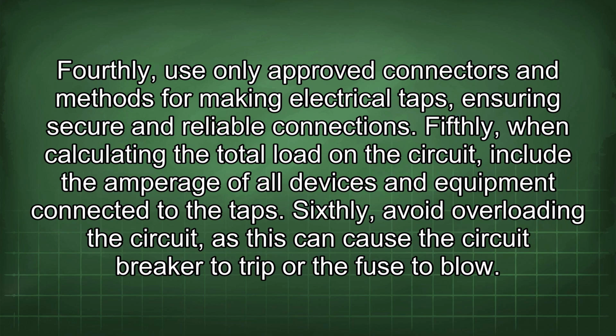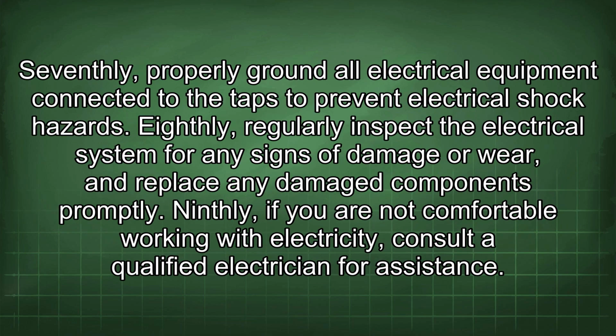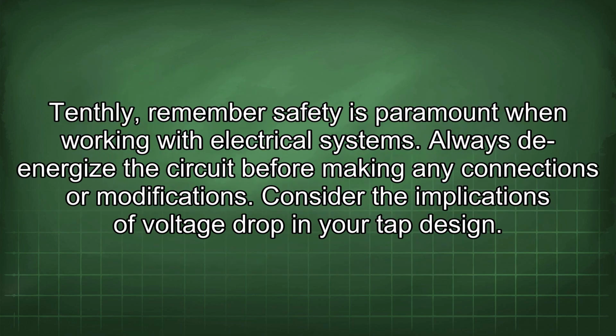Fifthly, when calculating the total load on the circuit, include the amperage of all devices and equipment connected to the taps. Sixthly, avoid overloading the circuit, as this can cause the circuit breaker to trip or the fuse to blow. Seventhly, properly ground all electrical equipment connected to the taps to prevent electrical shock hazards. Eighthly, regularly inspect the electrical system for any signs of damage or wear, and replace any damaged components promptly. Ninthly, if you are not comfortable working with electricity, consult a qualified electrician for assistance. Tenthly, remember safety is paramount when working with electrical systems.